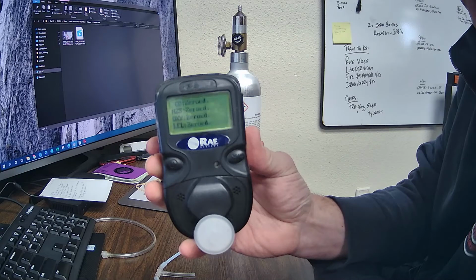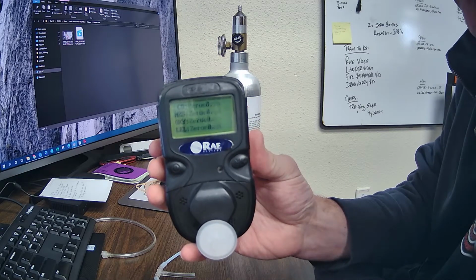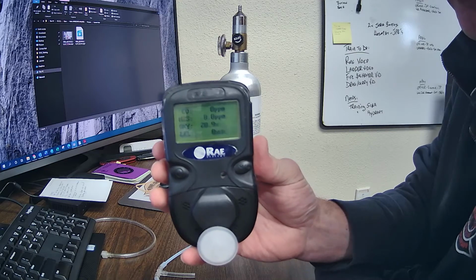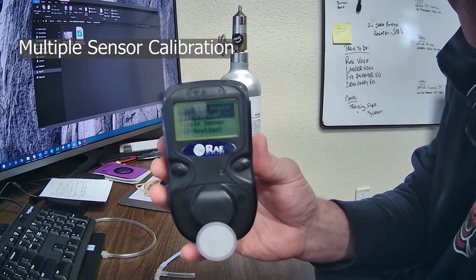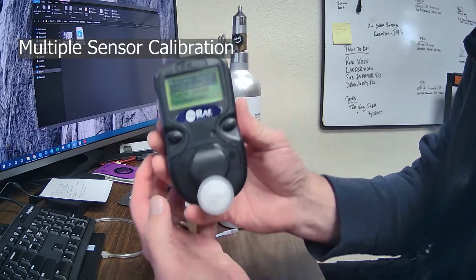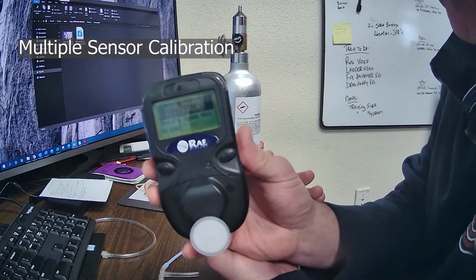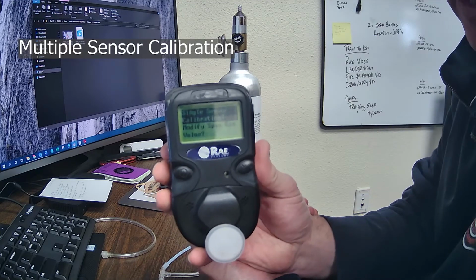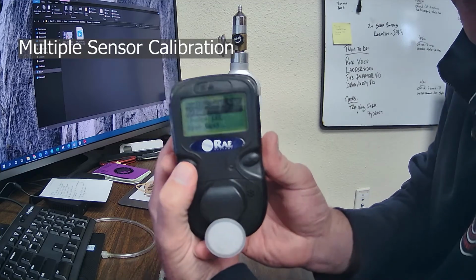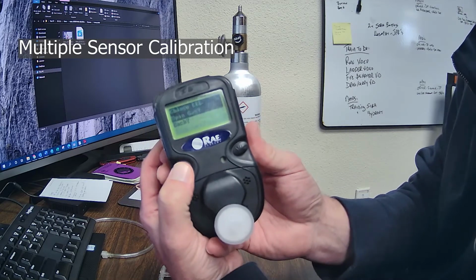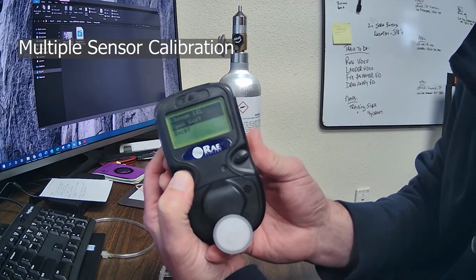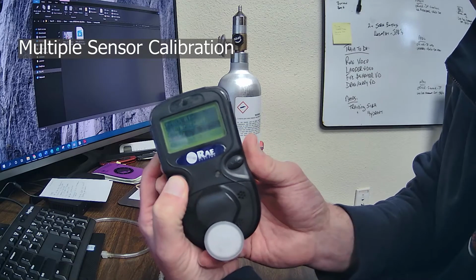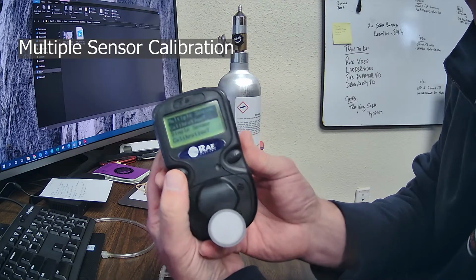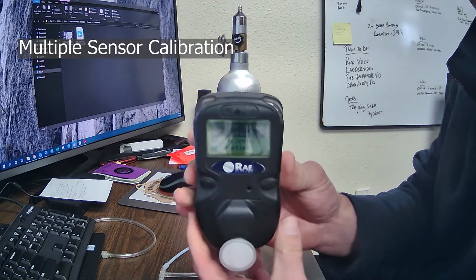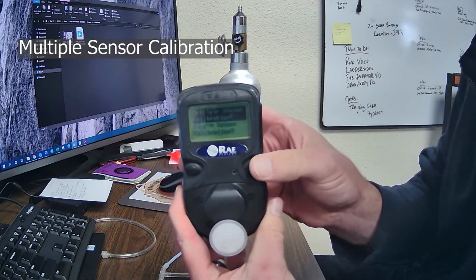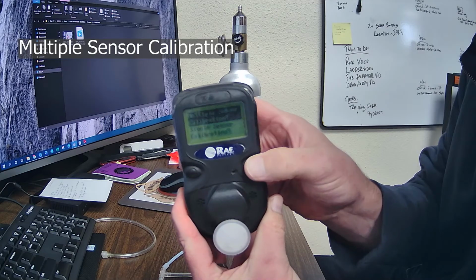So it zeroes out. CO zeroed, hydrogen sulfide zeroed, oxygen zeroed, LEL zeroed, and then it takes us back to the calibration mode. Perfect, because we want to do that. The next choice we have is a single sensor calibration. We don't want to do that. We want to do all of them. Modify span gas, change LEL. We don't want to do that. You can go back, and you probably saw that I skipped right over the multi-sensor calibration. The multi-sensor calibration is the one we want to do. So it's darkened. We're going to select it. Boom. We're going to do that.